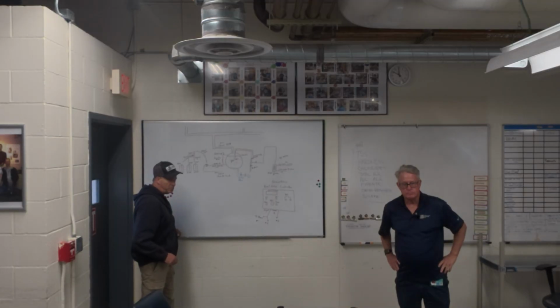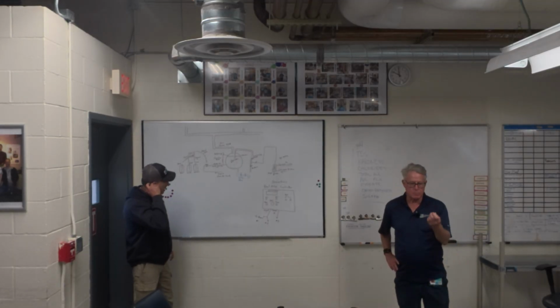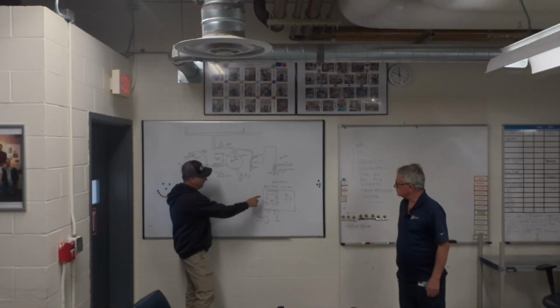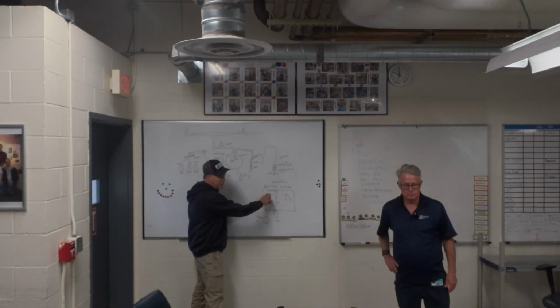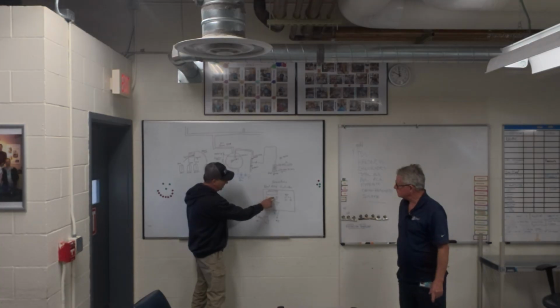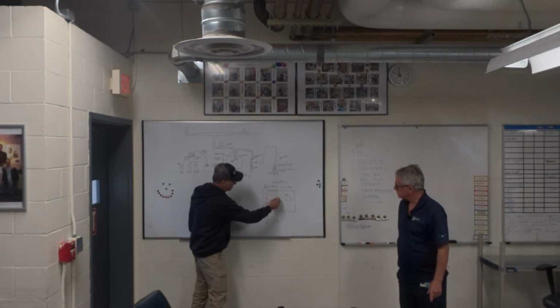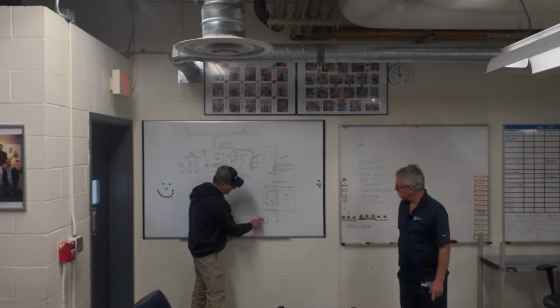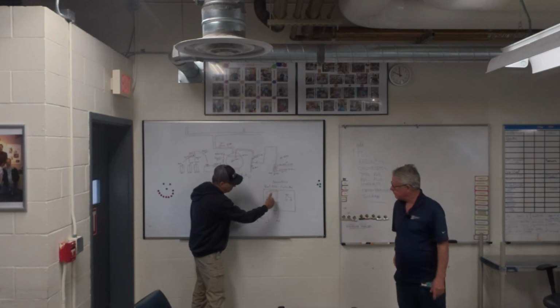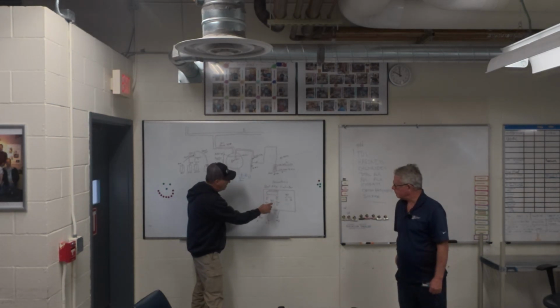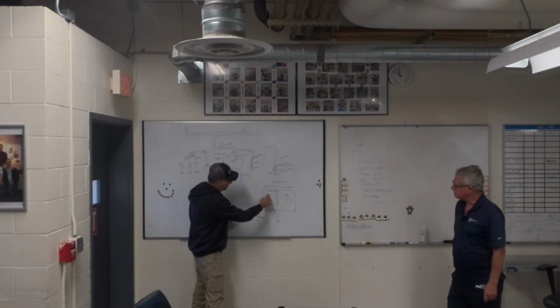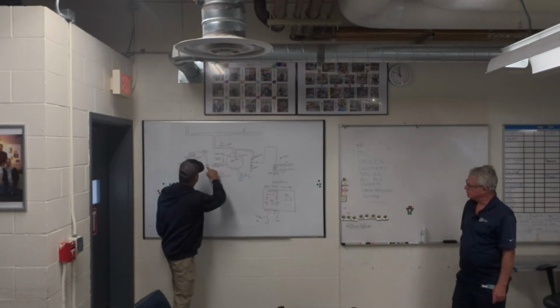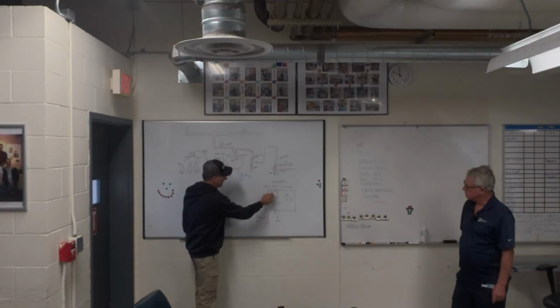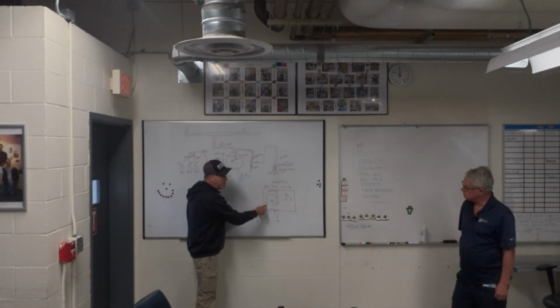The input connector, what is that seeing, your input? Yeah, that's coming directly off your flow meter. There's a pulse count that can be expressed here, like every 5 gallons. You can set this up here, the accumulator. This is channel 1, channel 2, right? Channel 1 takes care of both OX21 and B200. Channel 2 takes care of the steam line conditioner. So the controller has 2 channels. For this channel, you might set it up to every 10 gallons of input, every 10 clicks, it'll initiate a sequence for however long you want. Like, let's just run every 10 gallons, and run this channel for 5 seconds or 10 seconds.